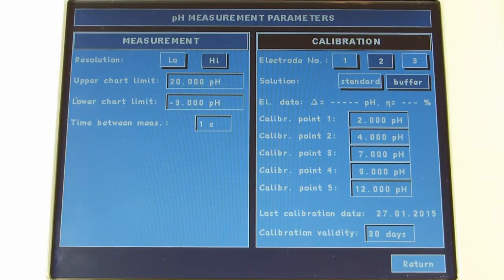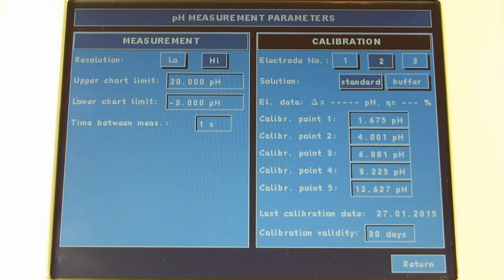Calibration parameters. In the calibration solution position, it is possible to choose buffer or standard. Buffer, calibration with use of buffers. Values entered in the memory by the user. Calibration may be made in 1 to 5 points. Standard, calibration in standard solutions. Calibration with use of standard solutions prepared according to the NIST. It facilitates work because the standard values are stored in the meter's memory. When the standard option has been chosen, the meter recognizes the standard's pH value, which corresponds to the current temperature. There is no need to warm up or cool down the solutions.